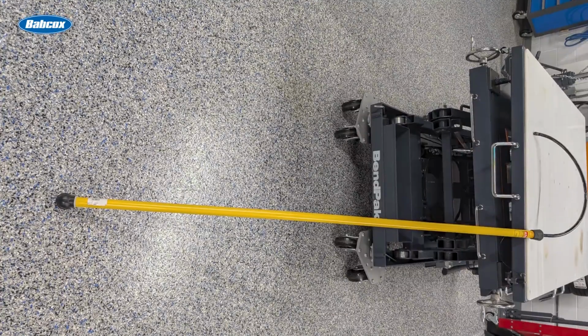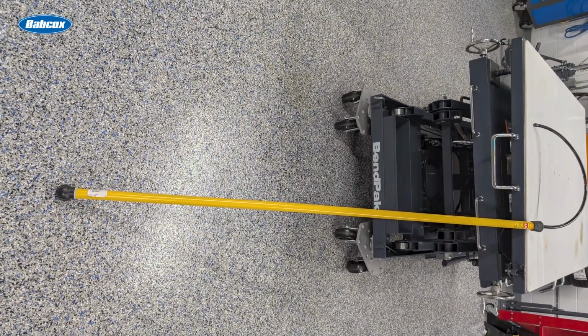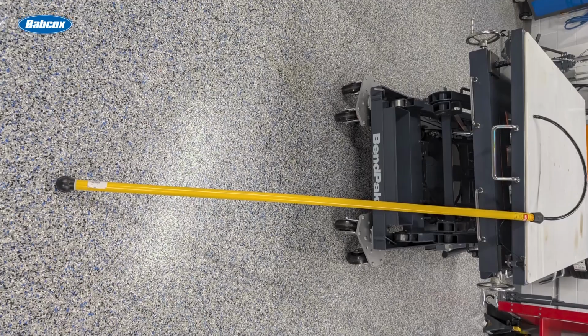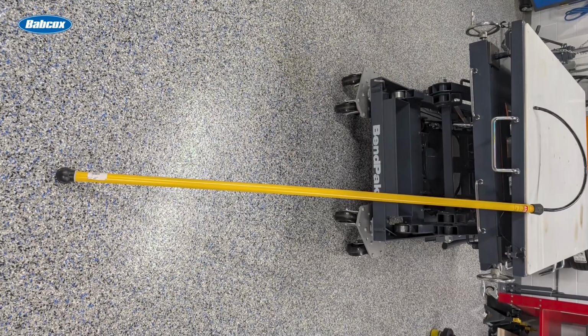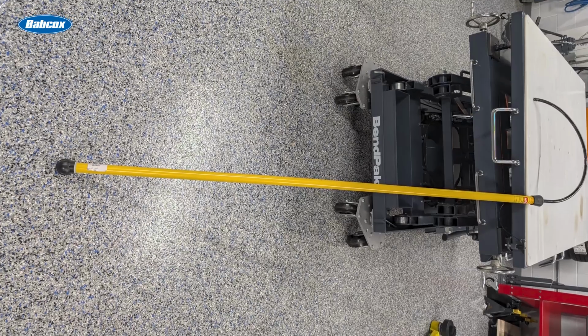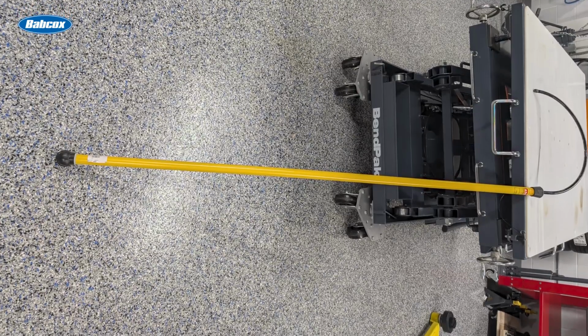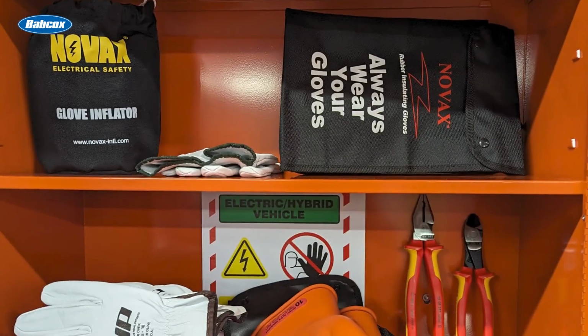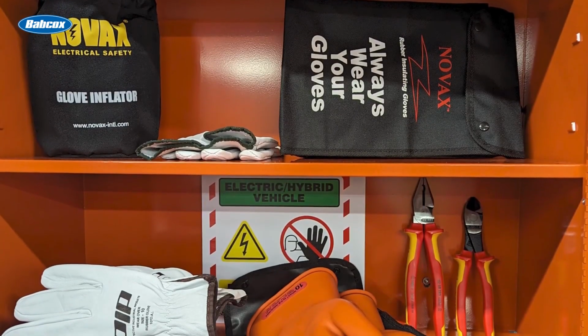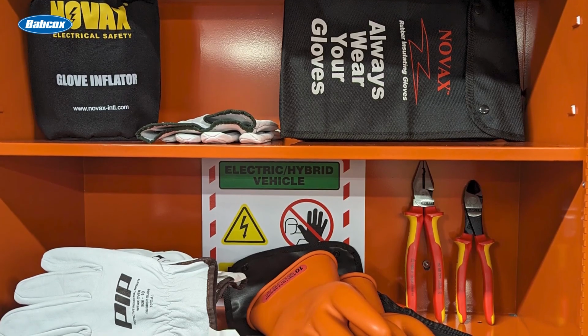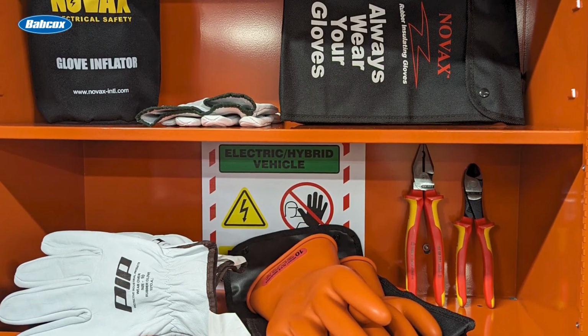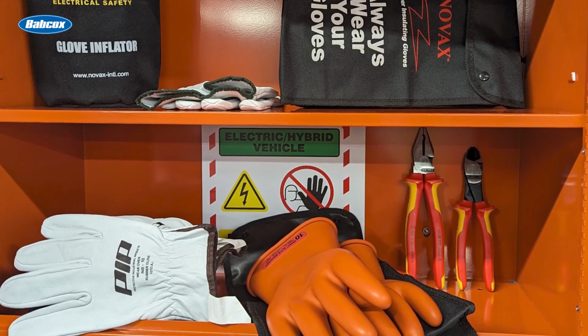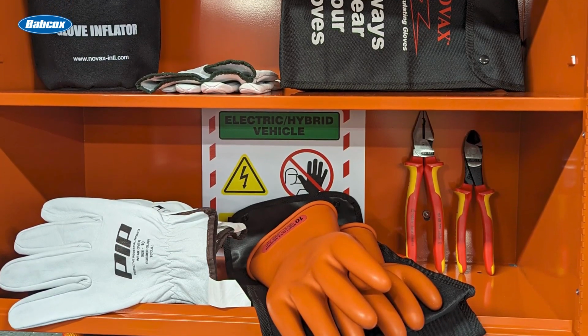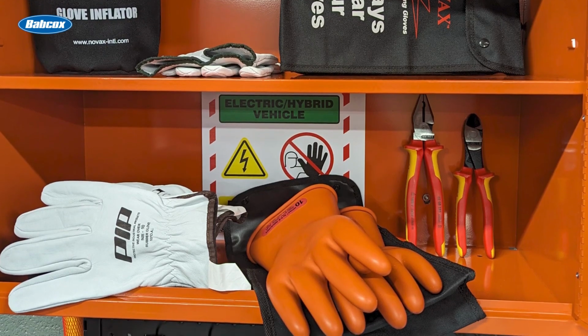In addition to cordoning off the area, shops need to be equipped with an insulated rescue pole, which, in the event of an accident, allows someone to safely pull the technician away from an electrical source. The technicians themselves must wear insulated safety gloves rated and designed to handle high voltage, and the gloves need to be checked prior to each use for tears, cuts, leaks, or damage that could allow electricity to travel.